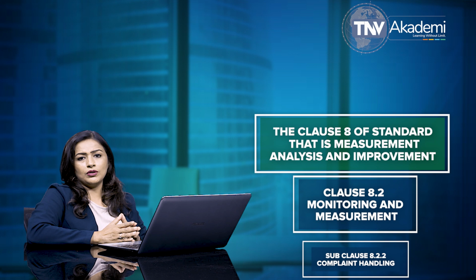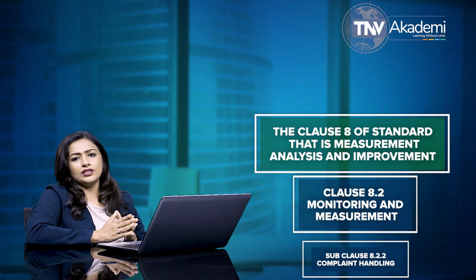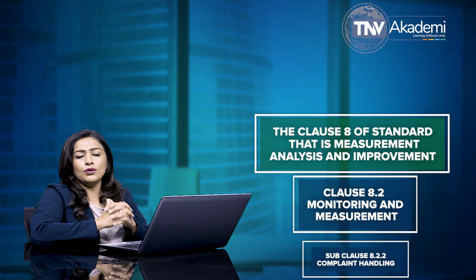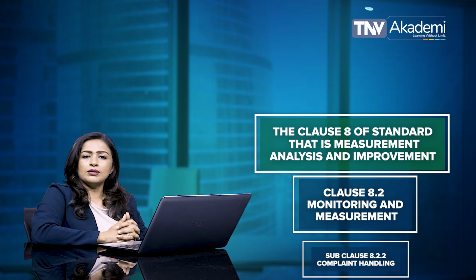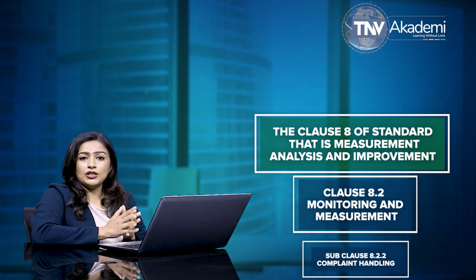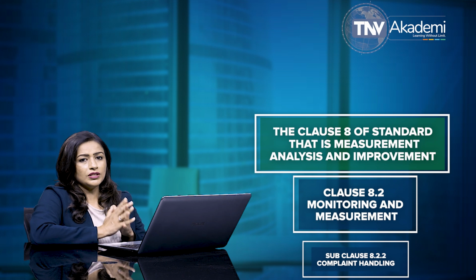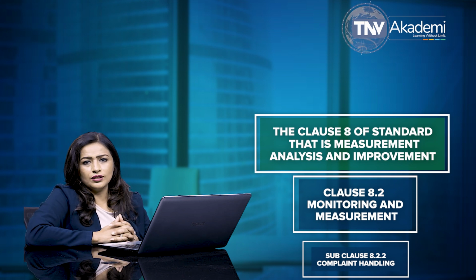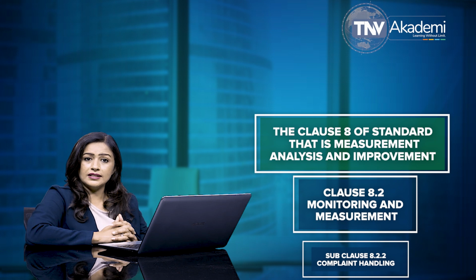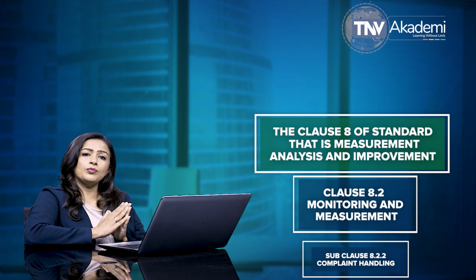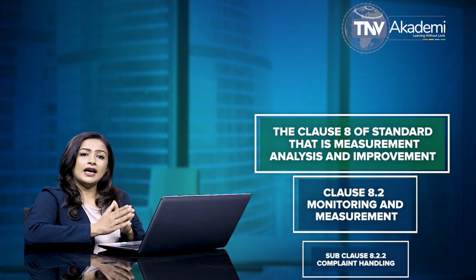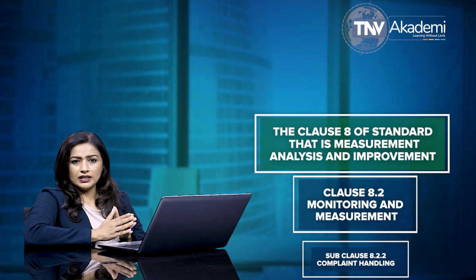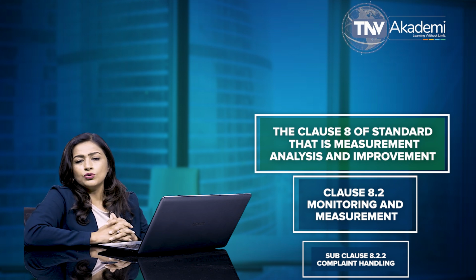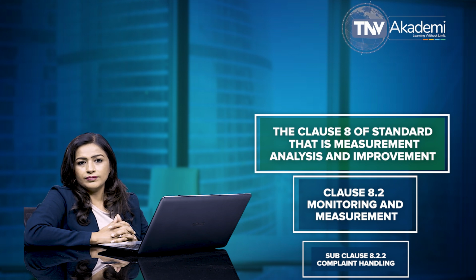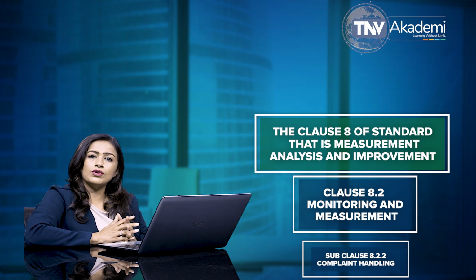As per this subclause, if an investigation determines activities outside the organization contributed to the complaint, then relevant information is required to be exchanged between the organization and the external party involved. Lastly, as per this subclause 8.2.2, the complaint handling records are required to be maintained by the organization to meet the requirements of the standard ISO 13485:2016.